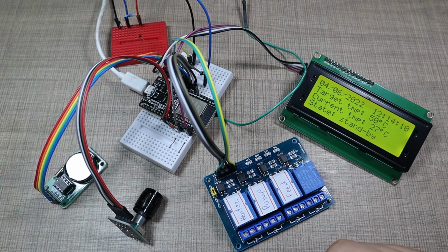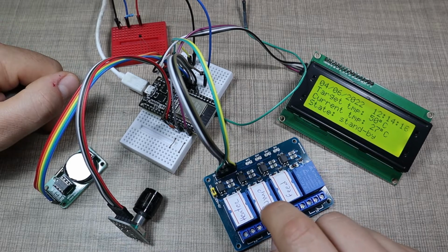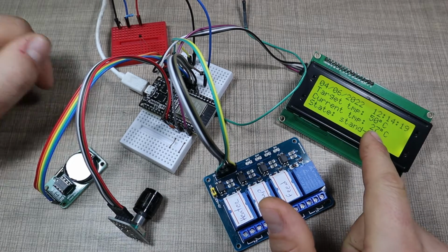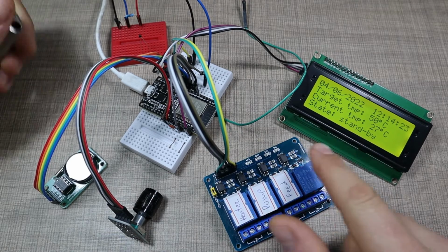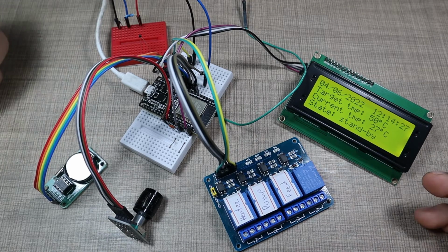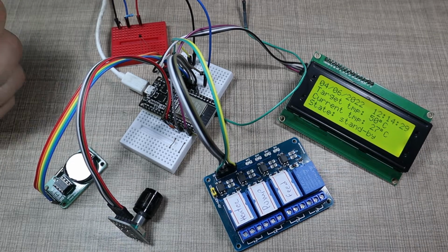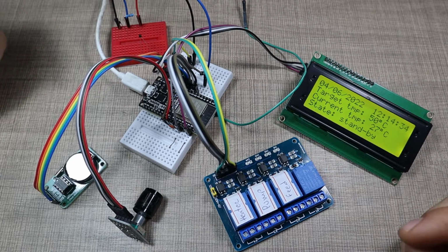And the first one is the function that controls the output of the pump. Anytime that we have enough temperature difference as set on the controller, we need to have the pump on no matter what's the state of the controller. So if we have heat available inside the boiler, then we need to distribute that heat throughout the system.